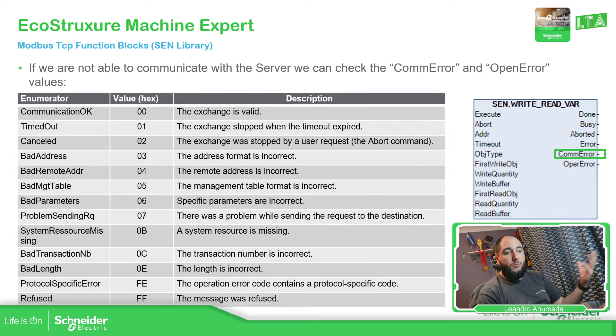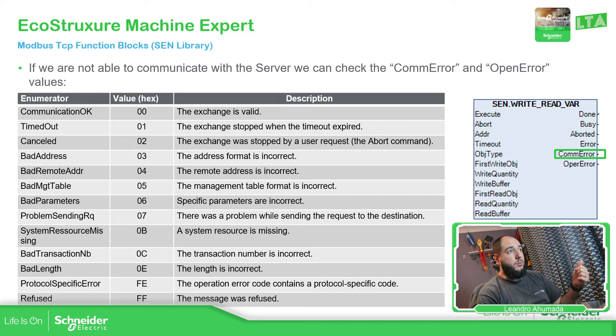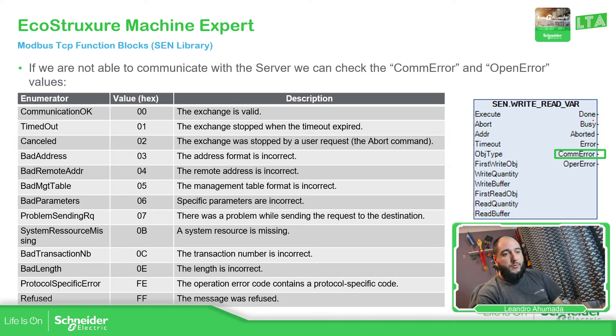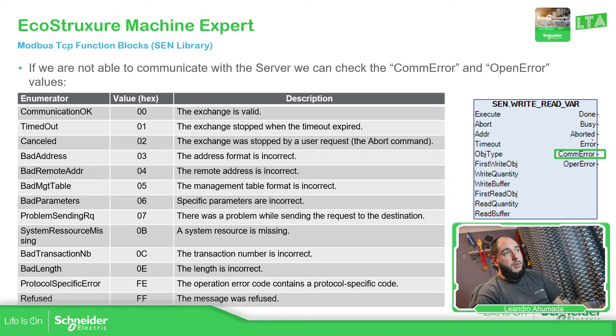We also have the possibility to make diagnostics. As soon as you execute this, you should be able to see the function block is busy. As soon as it finishes and everything is fine, then you should be able to see the Done output go true. If you are stuck on busy for some reason, you have the possibility to use abort and then you should see the Aborted output. If you execute again and receive busy and then error, check the COM error and OPER error outputs.